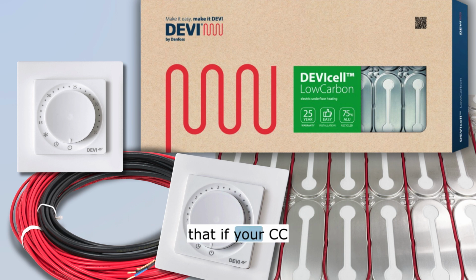What's fascinating here is that if your CC distance is too wide, you end up with cold spots on your floor. If it's too tight, you create concentrated hot spots. And those hot spots can overheat the system or damage the flooring above. Exactly, and there are strict spacing rules governing this placement. Any obstacles, like a drain or a pipe, need a clearance of at least half the CC distance. And under absolutely no circumstances can the heating elements ever cross or touch each other. Because if they touch, you are instantly doubling the heat density at that exact microscopic point. Yes, it will literally melt its own protective insulation and short out entirely.